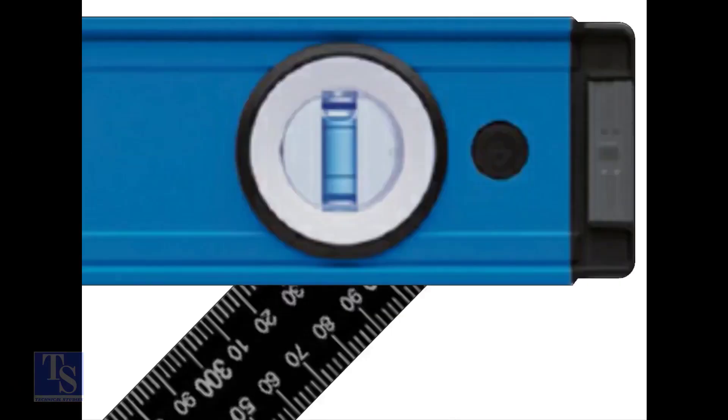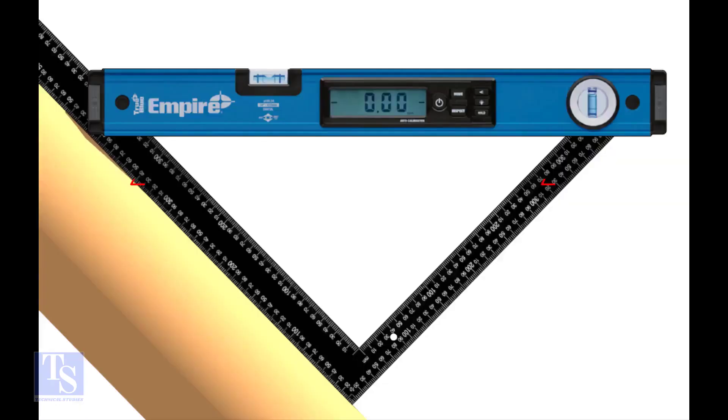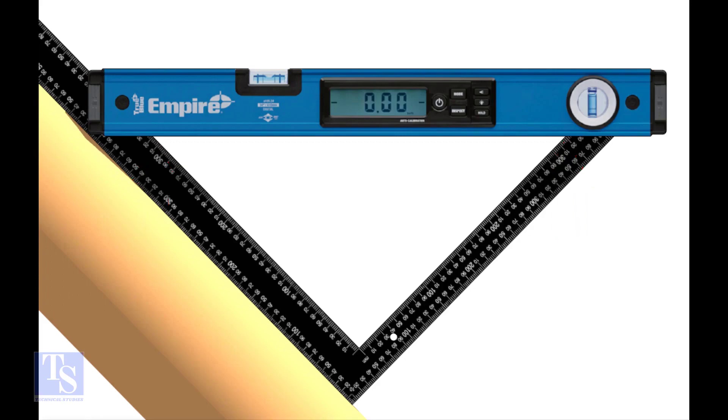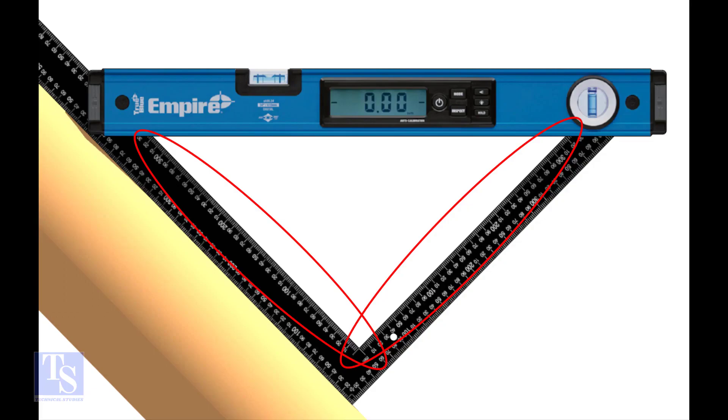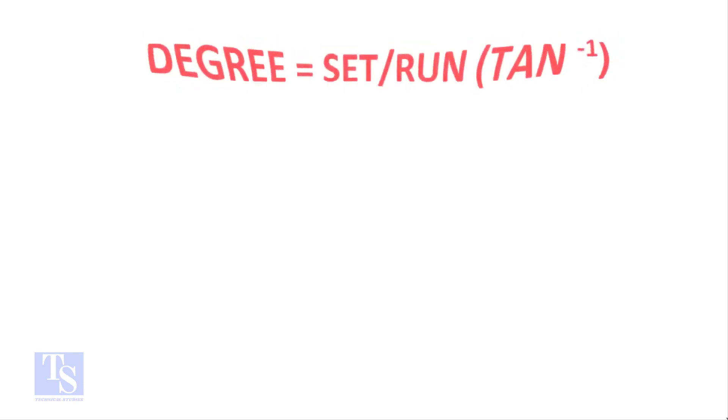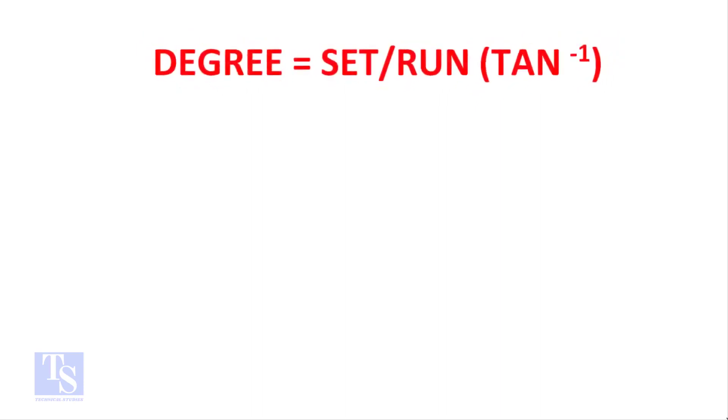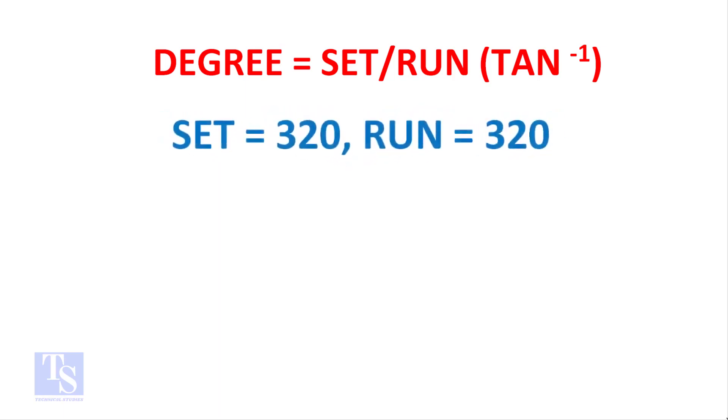Now we have a fraction of the set in the run of the pipe. Let us apply the tan theta rule. Degree equals set divided by run, shift tan. Set and run, both are 320 millimeters.